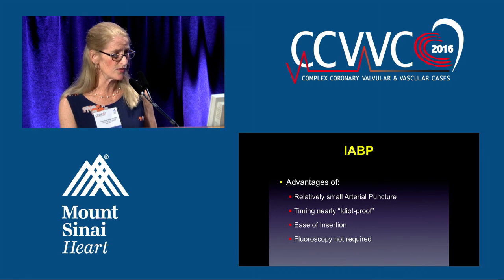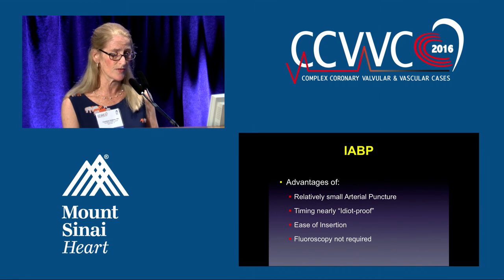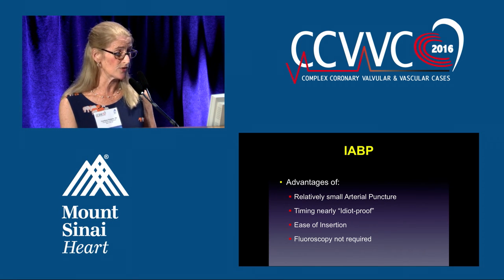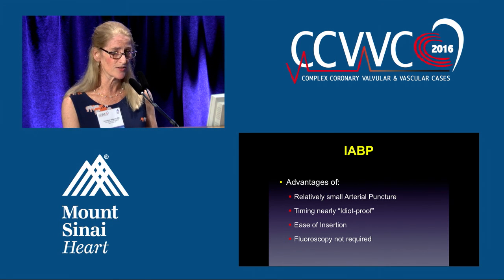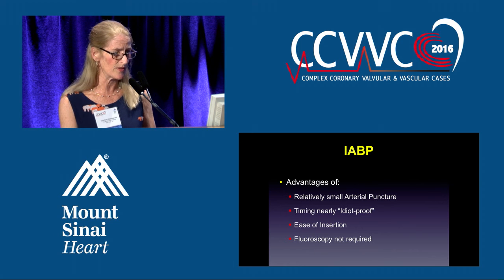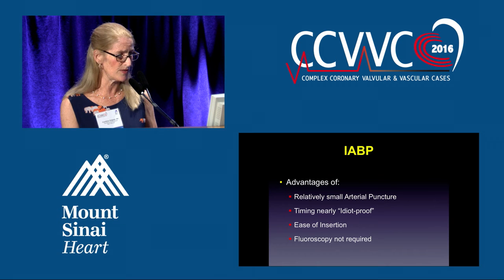The advantages to using an intra-aortic balloon over other devices are that it's delivered through a relatively small arterial puncture. It's now 7 French or less. The manufacturers have made timing of inflation and deflation almost idiot-proof. It's rare that the user has to tweak the timing at all. It's inserted through a very familiar femoral artery puncture, and it can be done at the bedside. You don't need fluoroscopy to place an intra-aortic balloon pump.